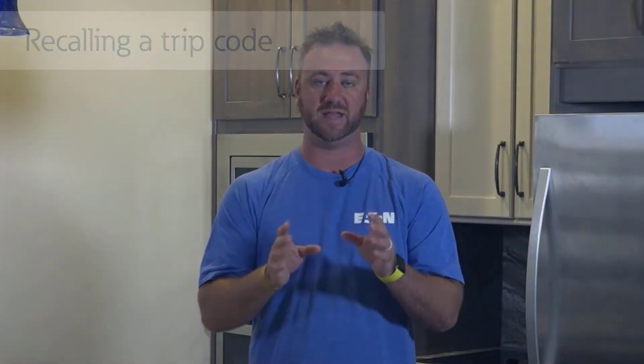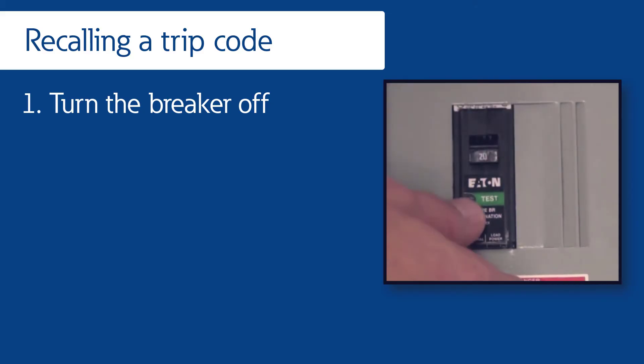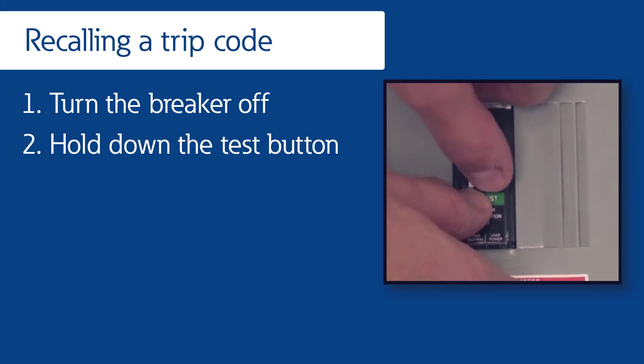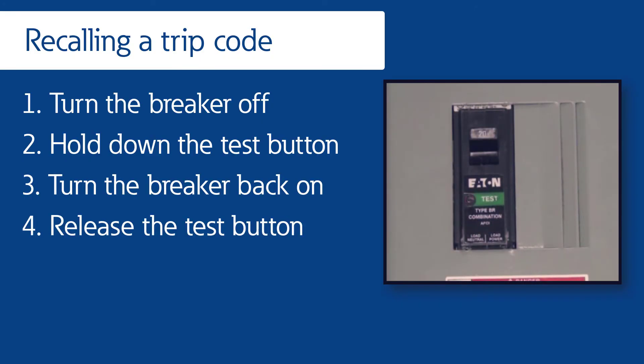With Eaton's electronic circuit breakers, you can determine the cause of the trip at a later time by following these steps: carefully turn the breaker off, hold down the test button, turn the breaker back on, then release the test button and the trip code will display again.